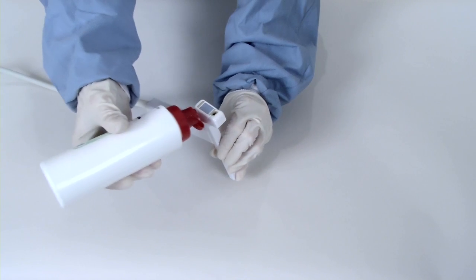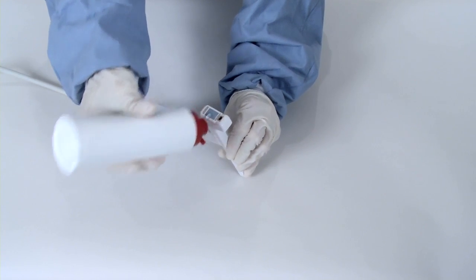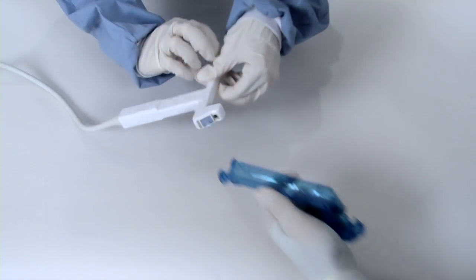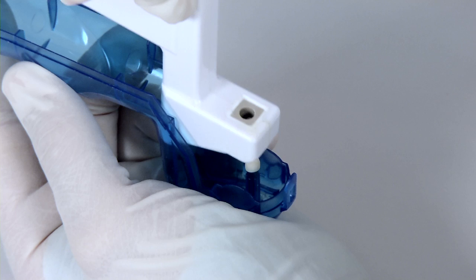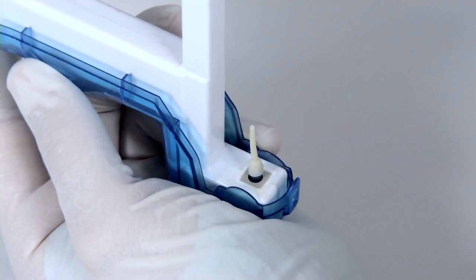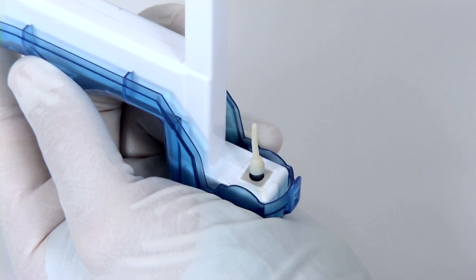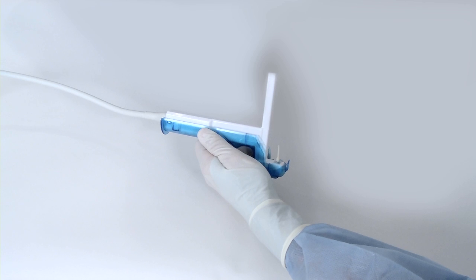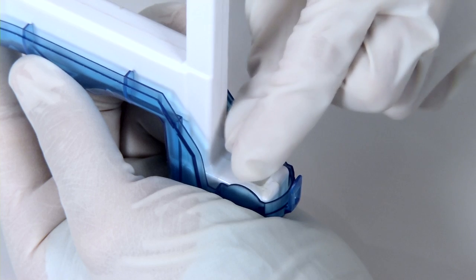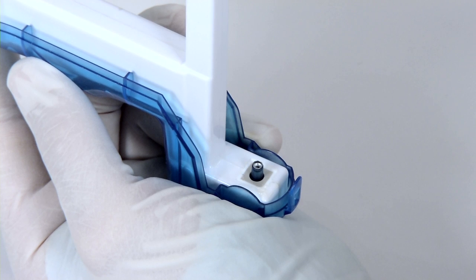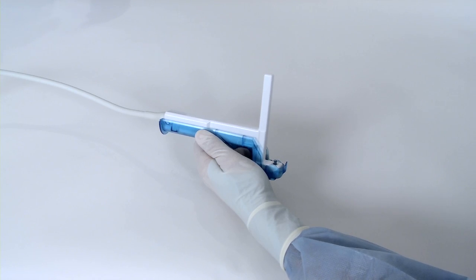The assistant applies a pea-sized volume of ultrasound gel to the acoustic window on the probe and lowers the probe into the bottom half of the probe shield until it is fully seated. Care must be used to avoid contaminating the practitioner's sterile gloves. The protective cap is gently removed by the non-sterile assistant, using care to avoid touching the sterile bottom shield.